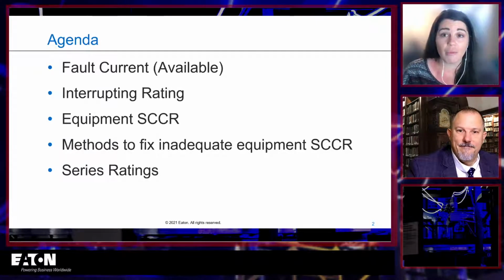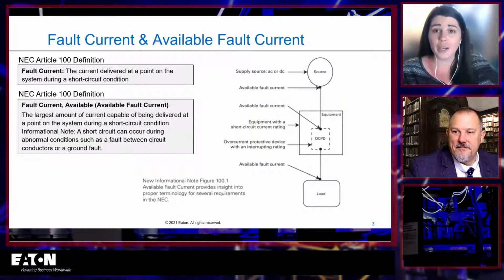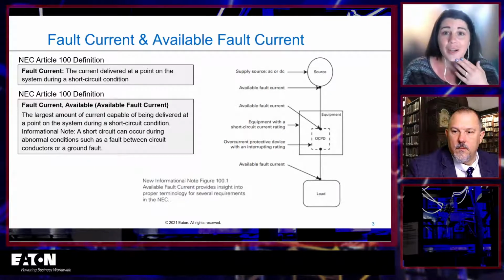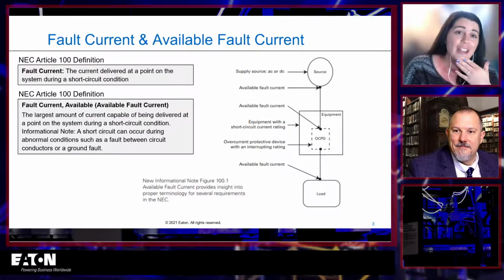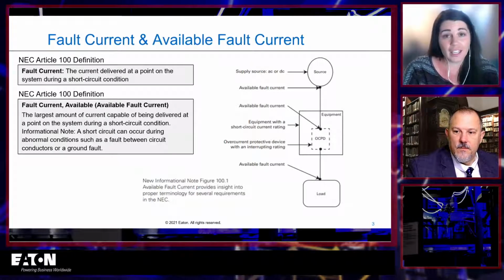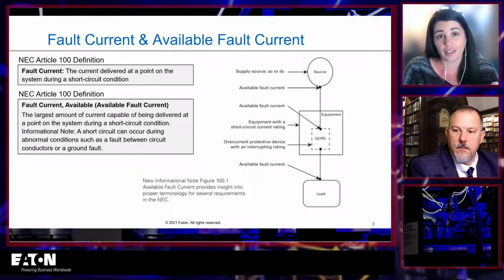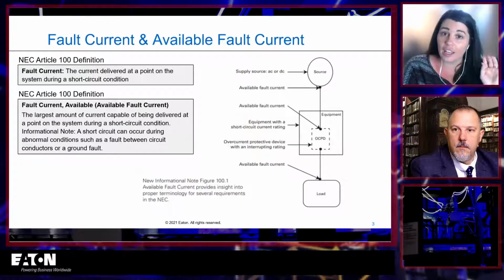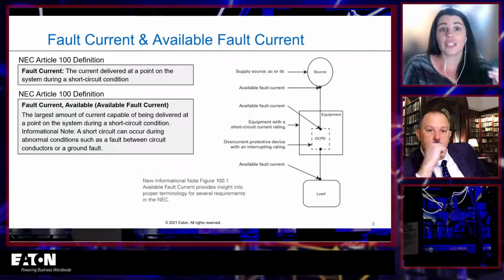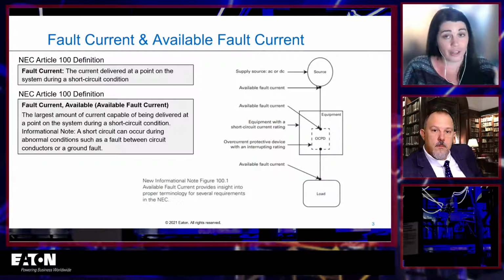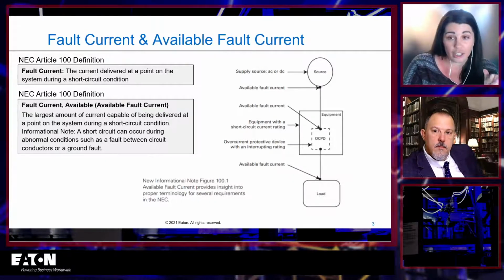So with that, we will just dive right into fault current. In the 2020 NEC, we finally got a definition for fault current. Can you believe that it took until the 2020 NEC before we got a definition? But we did. So the fault current is defined as the current delivered at a point on the system during a short circuit. So that's my fault current. I have a short circuit, however much current is there, that's my fault current. The available fault current, which is something else that we got a new definition for in 2020, is the largest amount of current that is capable of being delivered during a short circuit condition.